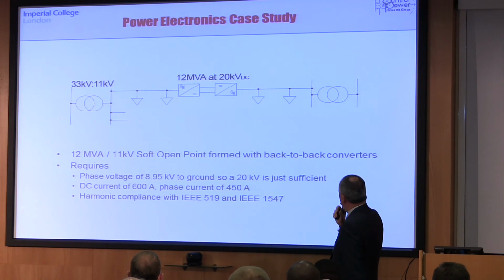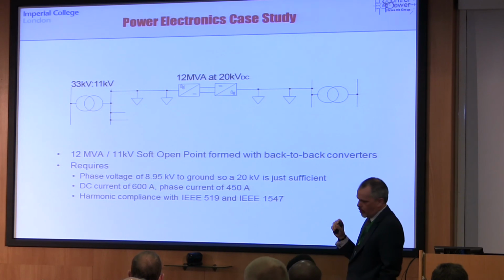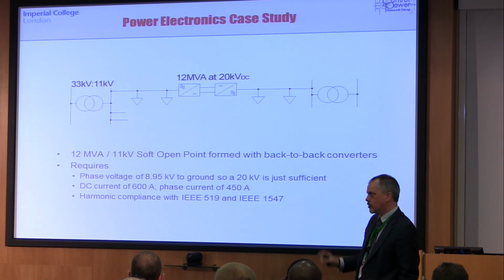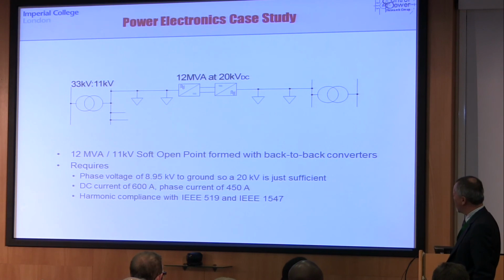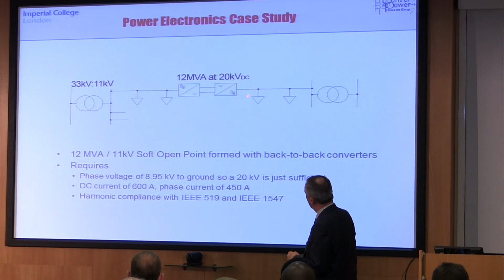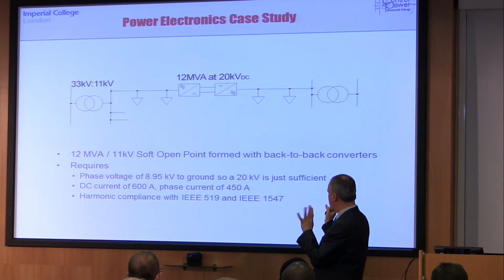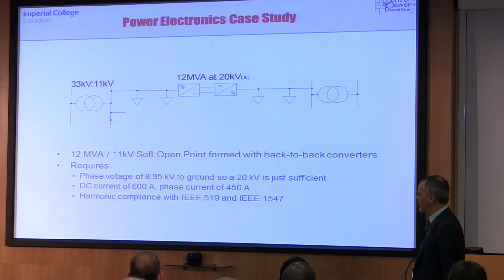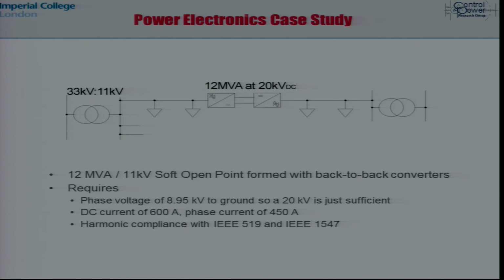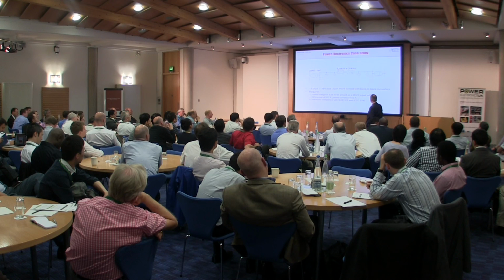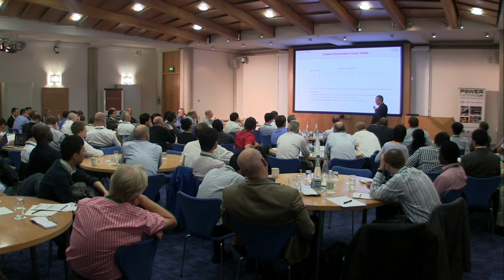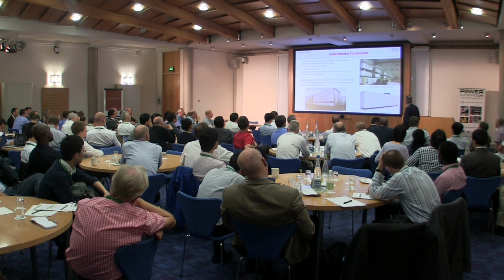Okay. Spend a few moments, I might have to go through this fairly quickly, on a case study. We did it a little while ago to look at just in terms of losses and volume and such, is it tenable to do a back-to-back converter at these sorts of ratings? This was for an 11 kV pair of feeders. Wanted to move 12 MVA out of the converters, and we were postulating a 20 kV back-to-back link and meeting harmonic standards.